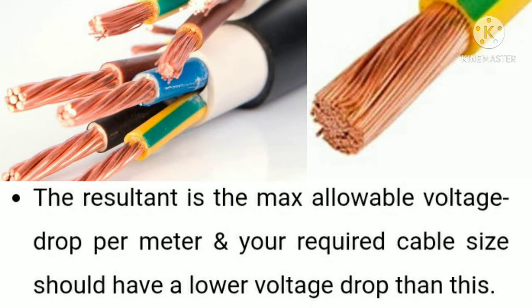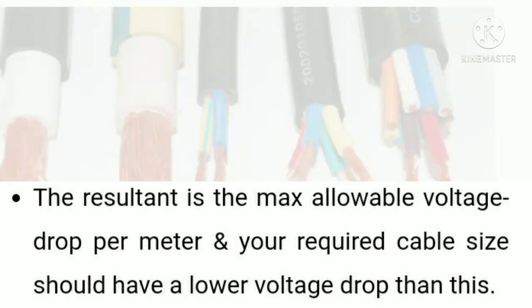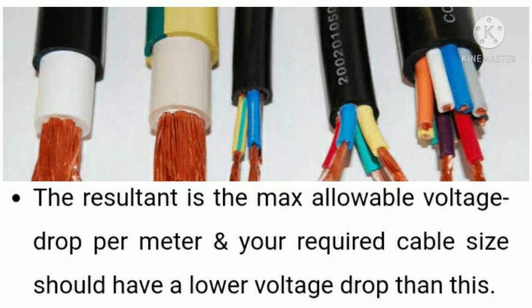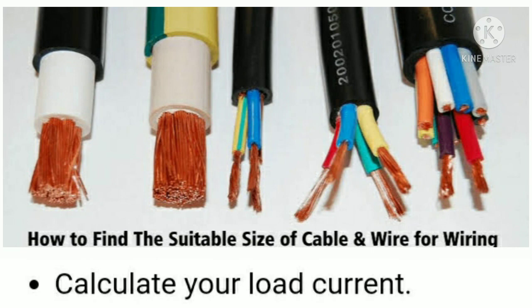The resultant of that division gives you the maximum allowable voltage drop per meter. The required cable size should have a voltage drop lower than this value. The maximum allowable voltage drop is 2.5 percent for any system, and both the load current and the voltage drop are important factors for choosing the right cable and wire.